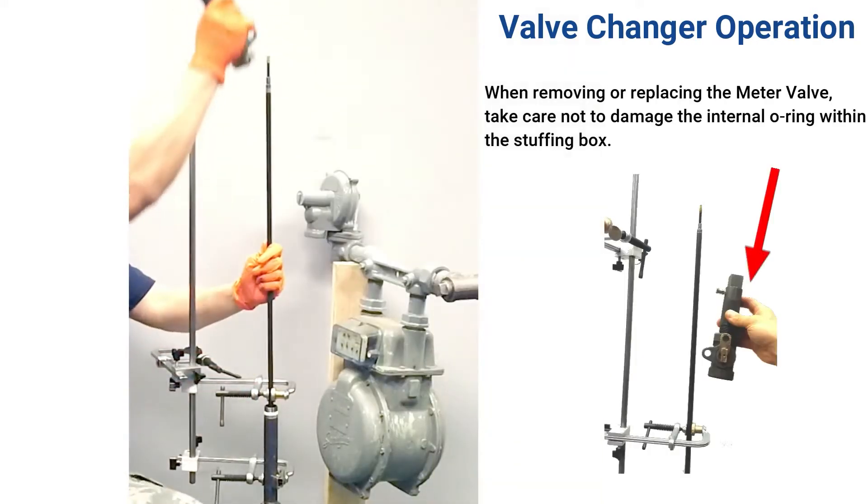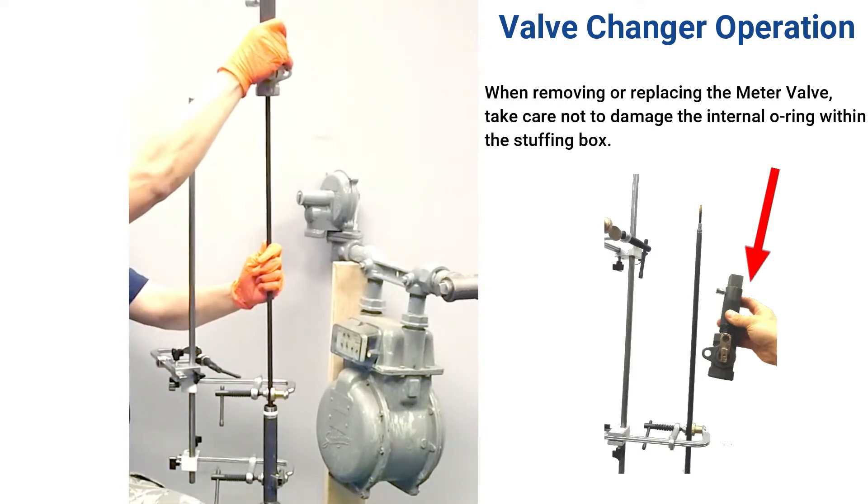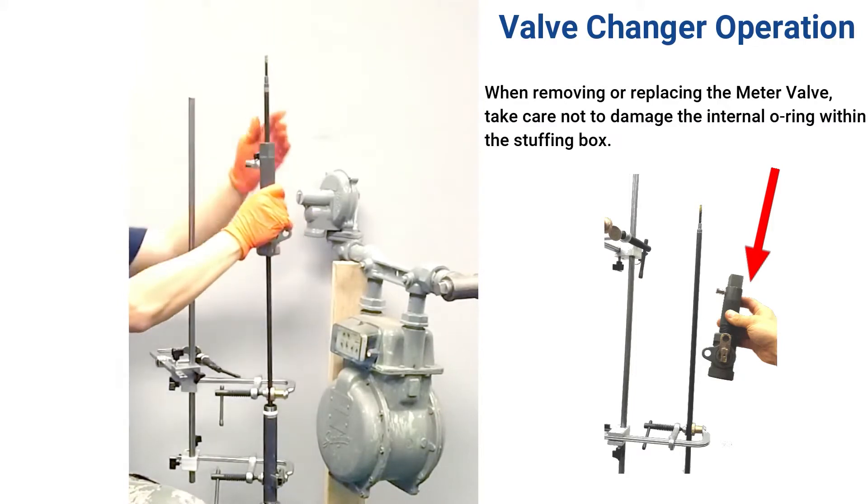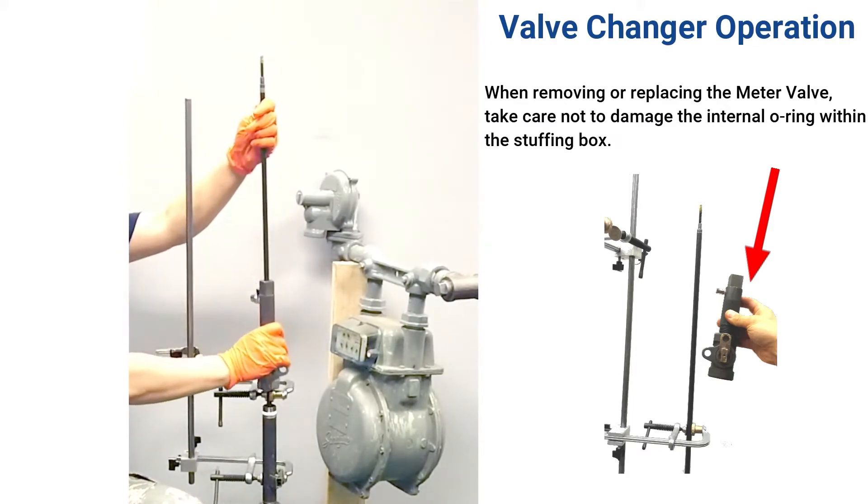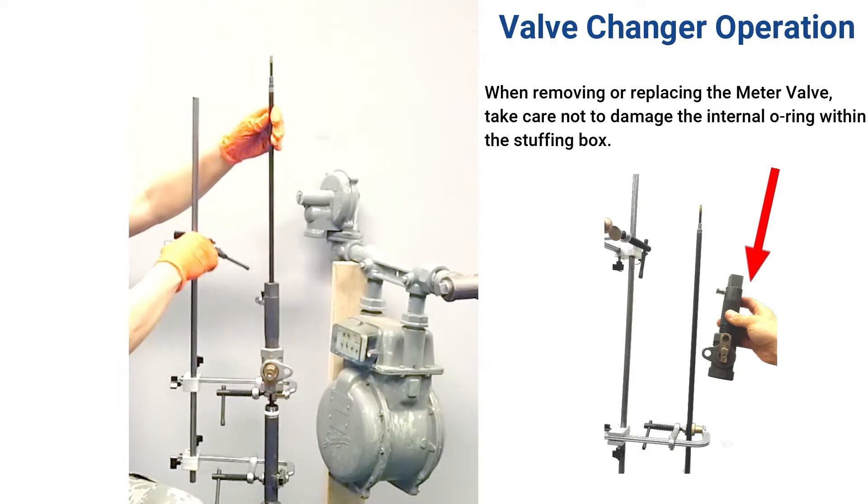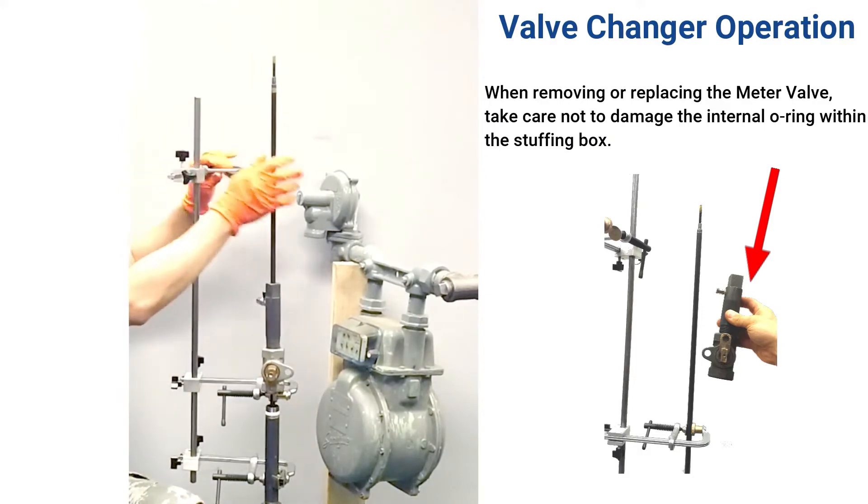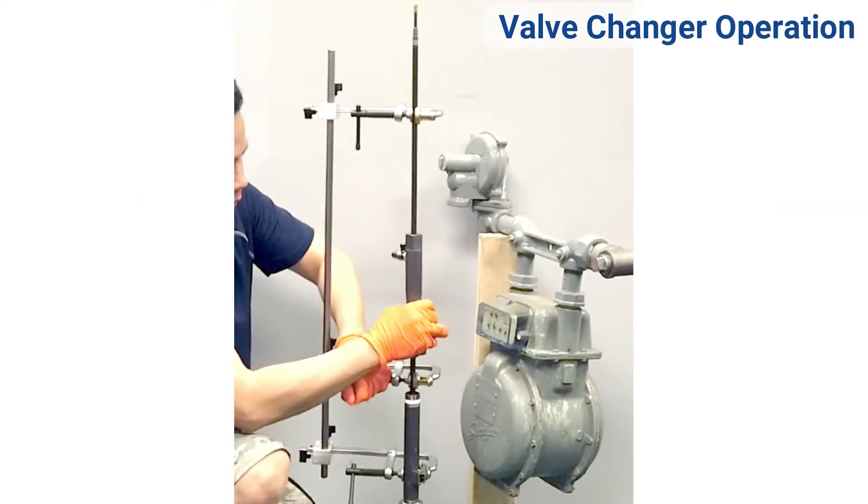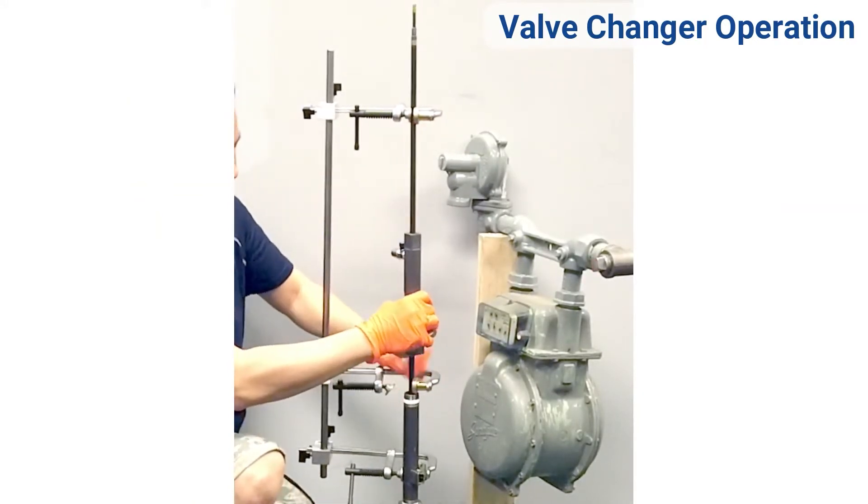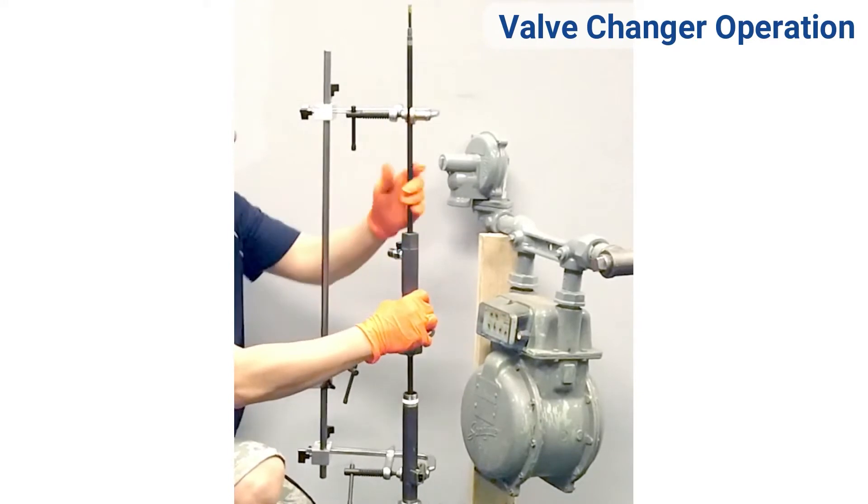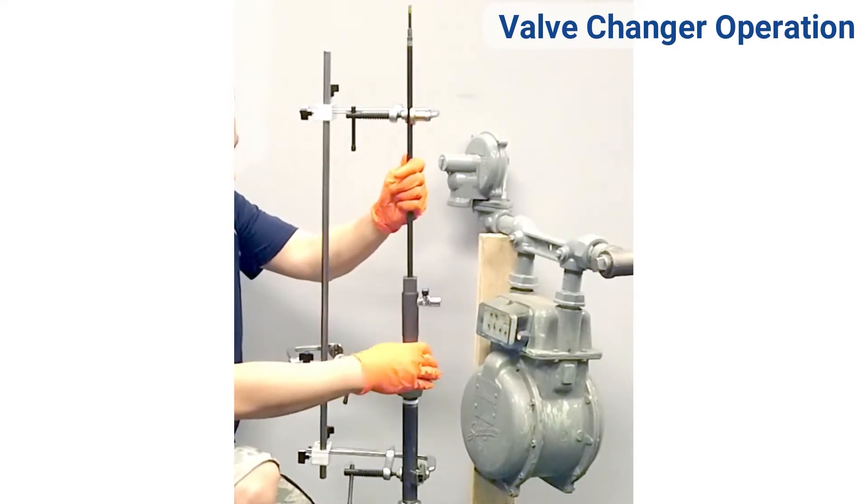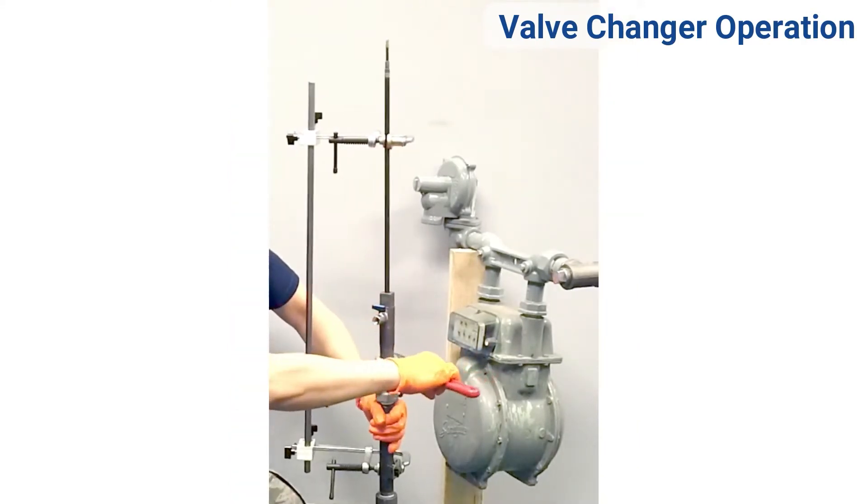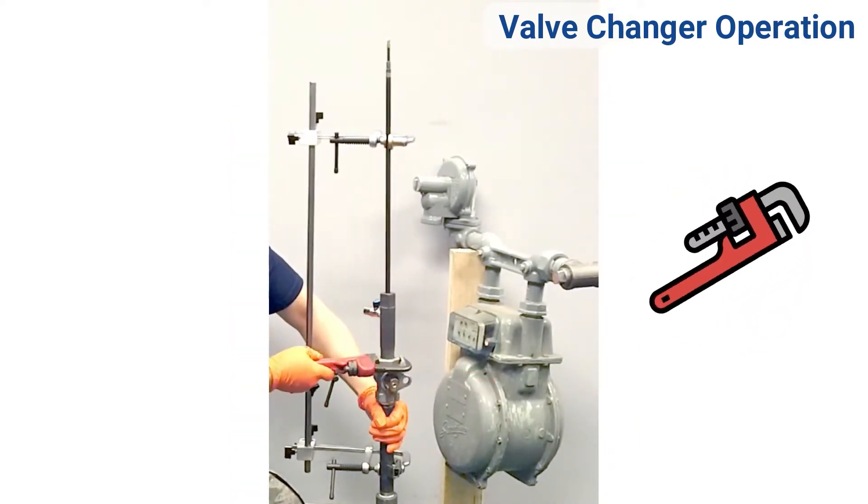Attach the new meter valve to the stuffing box and slide onto the shaft. Loosen and re-secure each clamp in order to travel down the shaft. Fasten the top clamp and remove the bottom clamp. Now fully tighten the meter valve onto the riser.